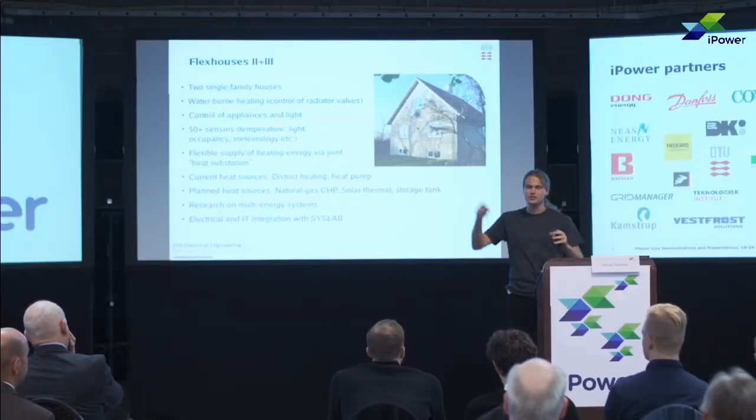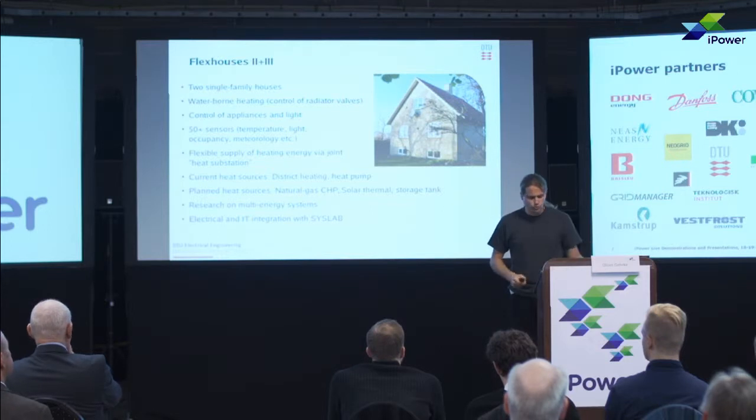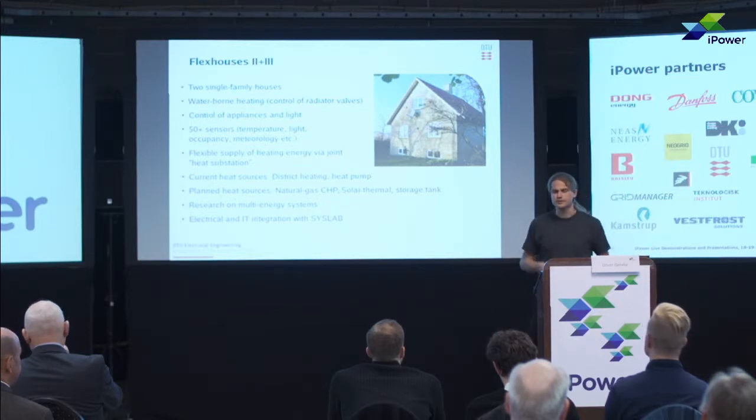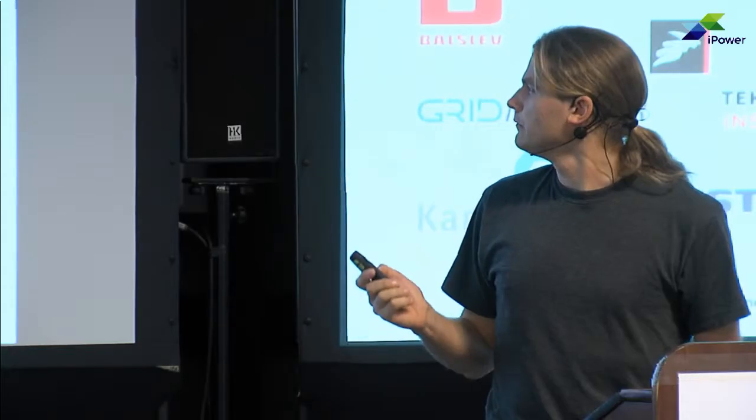So we started to build up a little, we call it a heat substation, where we can take different heat sources and heat storage and heat consumers, and also connect them together in different ways, control the flow, measure where the energy is going, and so on. To, for example, see how you could store excess electrical energy in district heating water to be used later when you need the heat. Right now we have basically a connection to the original district heating that was there, and we just got a big heat pump installed there that is able to supply both houses.